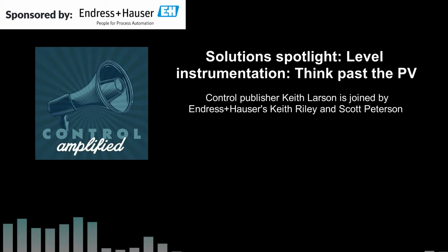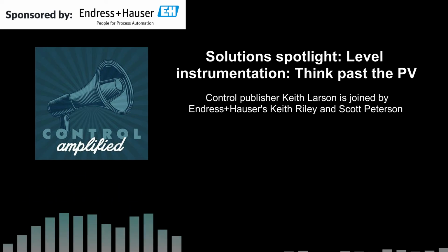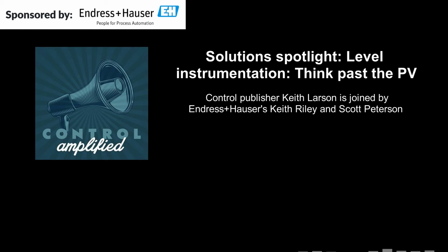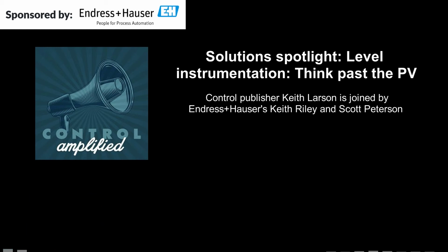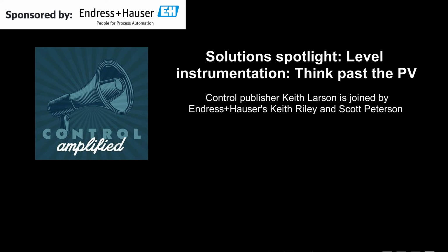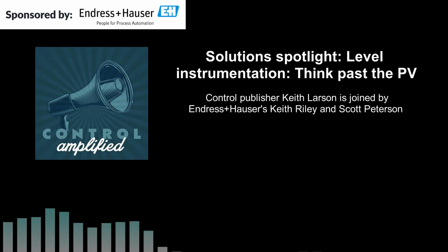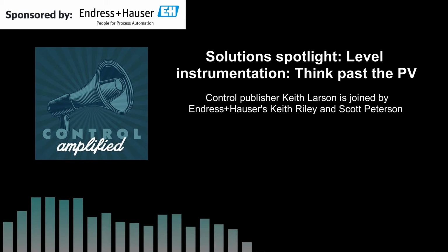And looking at operations, we see their role simplified as well. Usually error codes in the past were kind of undefined, hieroglyphic in nature. You had to look it up to even know what it meant. With suggested instrument guides to take the steps, if you look at the smart devices today and what we're offering, you have clear English directions and, again, instrument-guided steps to take. And then I guess finally looking at calibration and maintenance, we see simplification there as well. Calibration wizards, partial proof test wizards, like Keith had mentioned earlier. Each step is guided with simple directions, and that's all taking place while providing record keeping for the associated tasks as well.